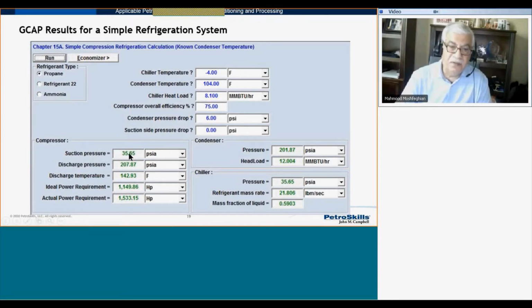And as you can see, the program calculated the chiller temperature and the compressor suction pressure, which is the chiller pressure. And by the way, the software uses the equation I said to calculate these properties and vapor pressure and so on. So I have everything. Let's focus on the key item. The compressor power requirement is 1,533 horsepower.